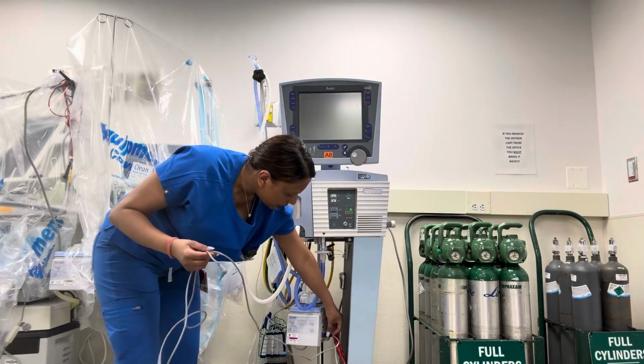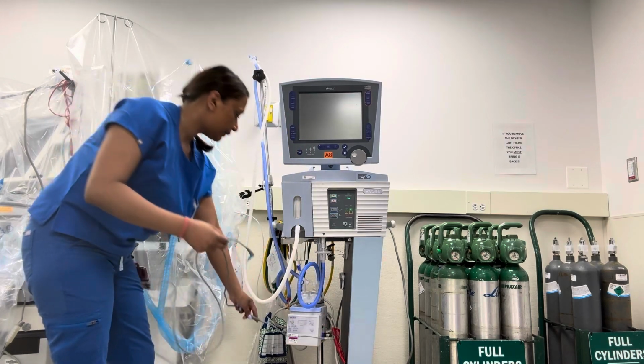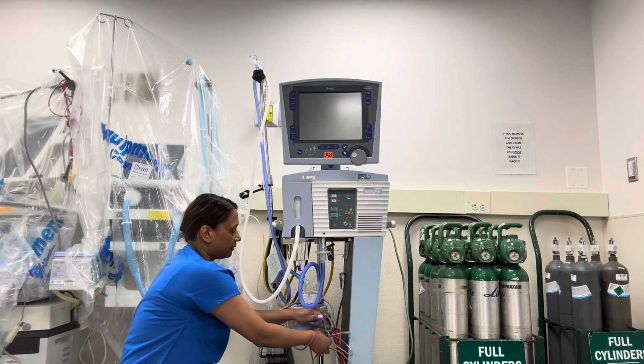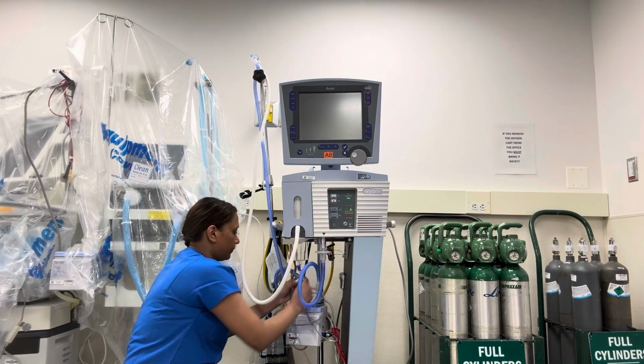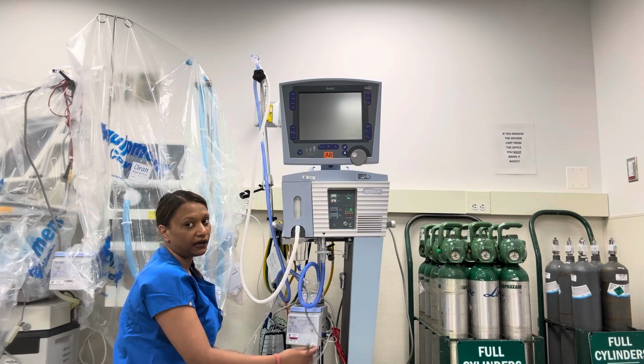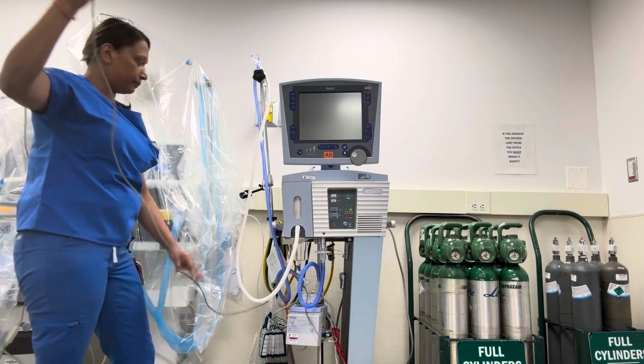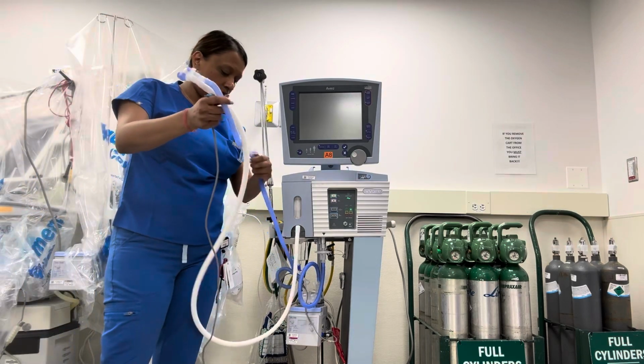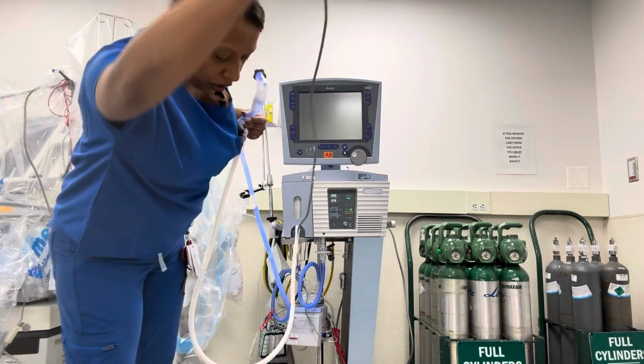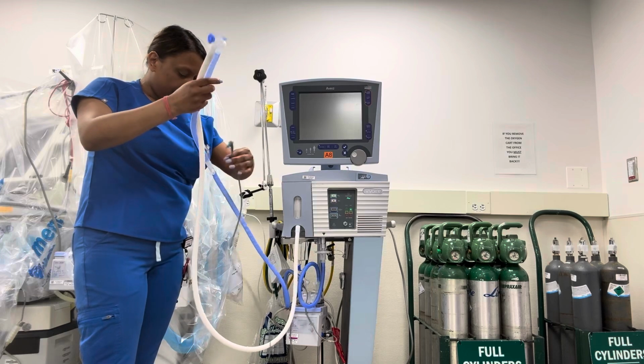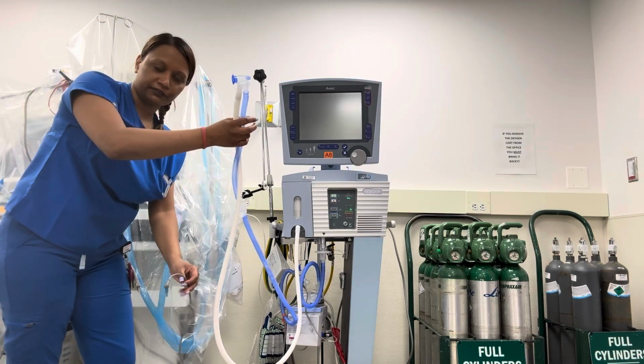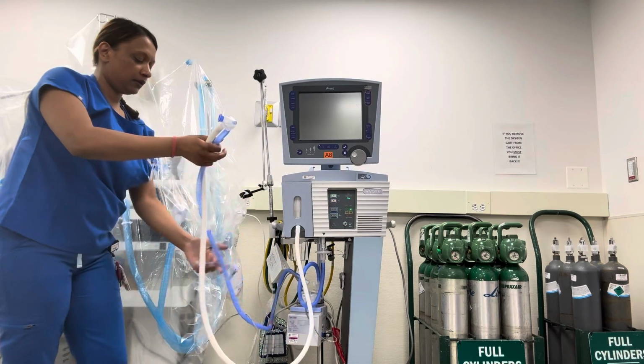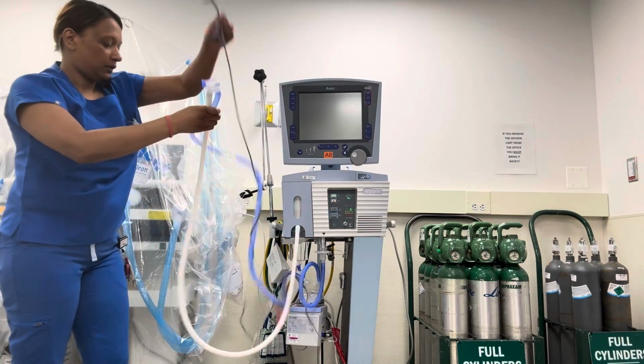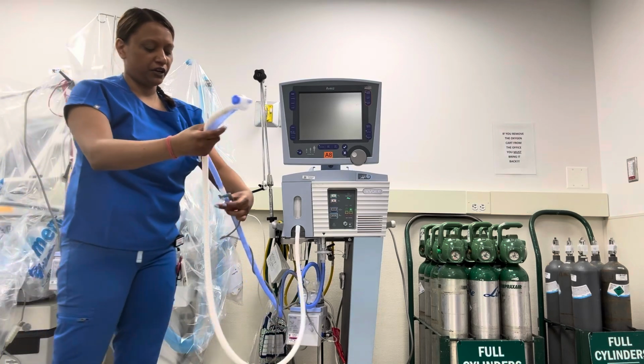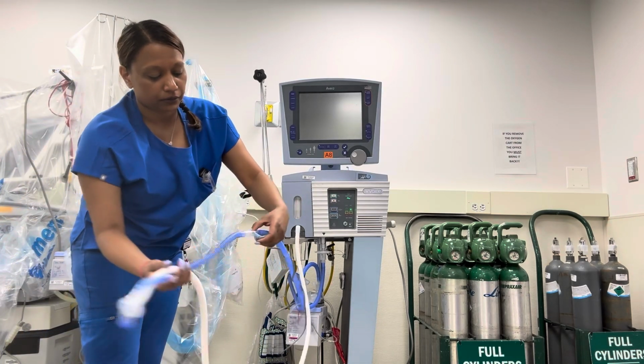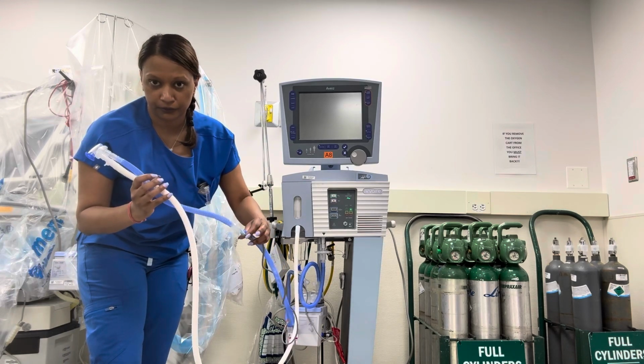Okay, so now this is going to go over here. Okay, see that? It fits in. It's like a lock and key. You can't mess this up. And then this will go to your longer limb, your inspiratory limb. Okay. So this long one, temperature probe, is going to go to your inspiratory limb. And what we do here, so it doesn't drag on the floor, is we just wrap it like this across, so it's not dragging on the floor, you know, and then it's gonna go here. So be mindful that it has to be in the inspiratory limb, okay?